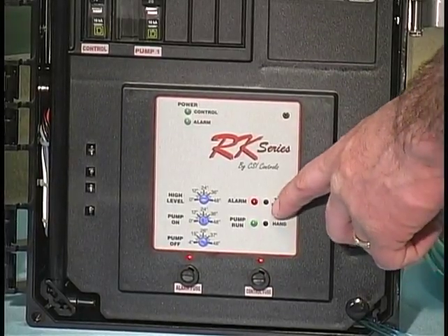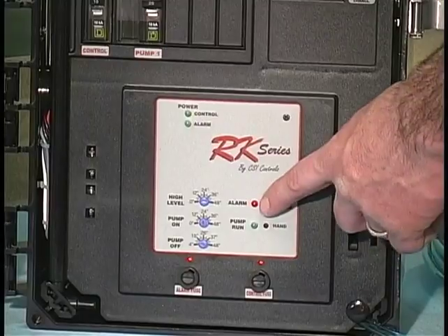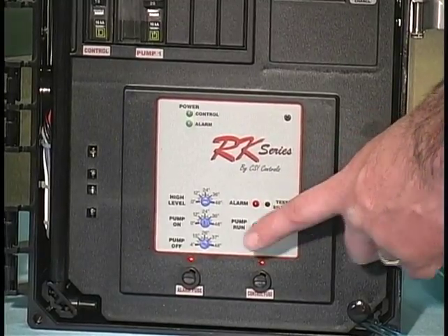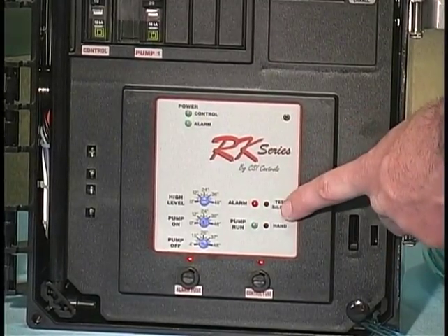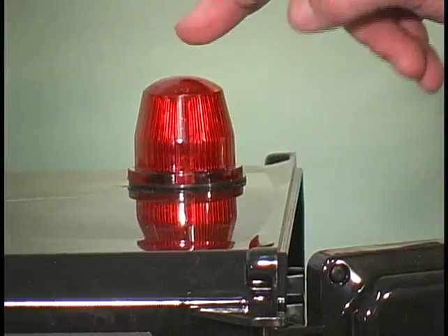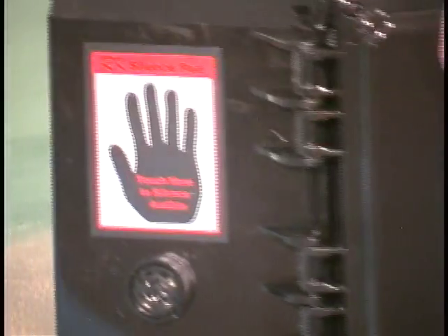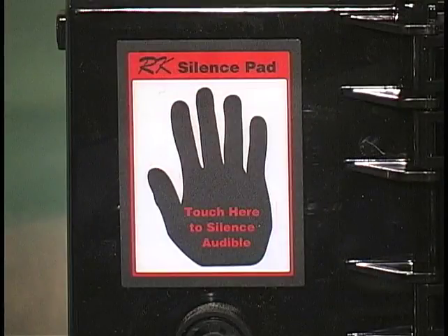It has a push to silence and test, so you can test your alarm, make sure your alarm function is working. You can also push that little black button to silence it. It comes with an alarm light on the top, a big red beacon, and then your silencing pad is on the side of the panel. Just rub your fingers across that and that will silence the alarm.